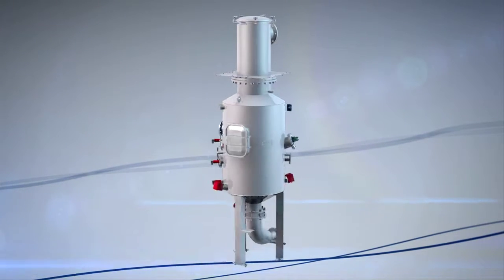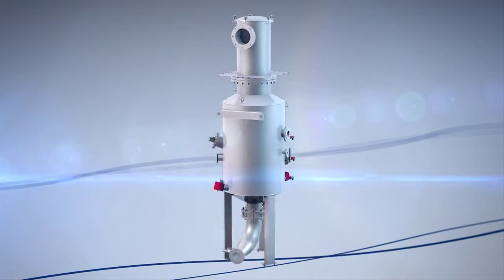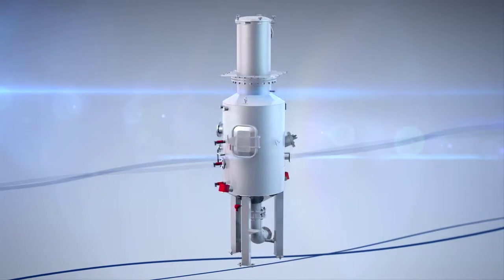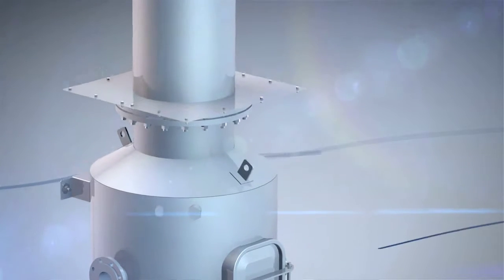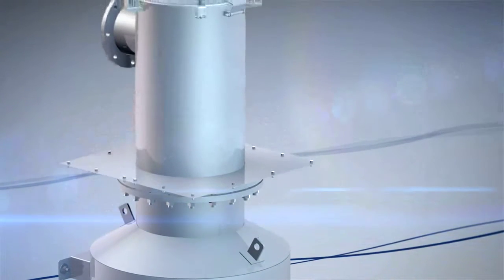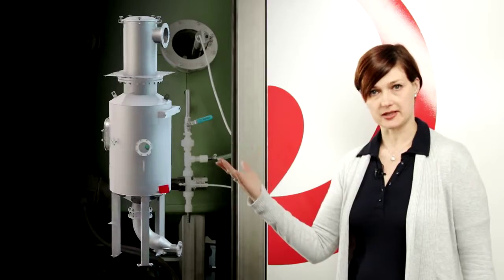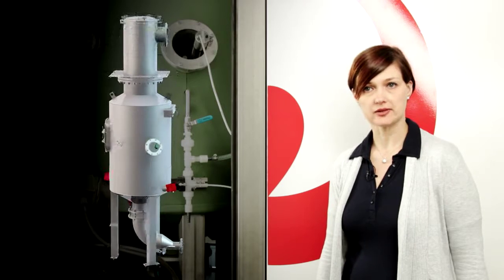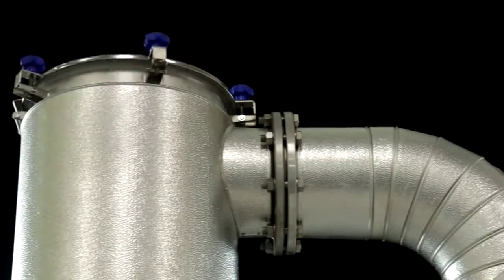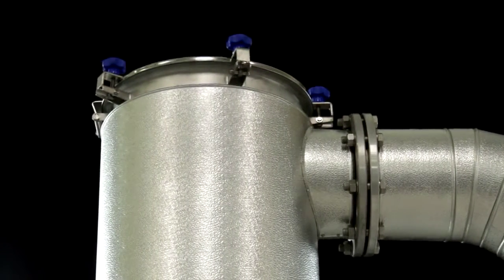Let's have a look at the shape of the boiler. We can see its geometrical construction and how this enhances the mist eliminator activity we saw previously. The goal is to have a different and more effective vapor distribution system. Here you can see how the boiler becomes more narrow. This is because we wanted to improve the impact speed on the mist eliminator. Here you can see how the boiler is higher. With this shape, vapor is evenly distributed and space for the vapor is increased. The final result is cleaner vapor, thanks to drop separation, with a remarkable improvement of the compressor performance and of distillate quality.